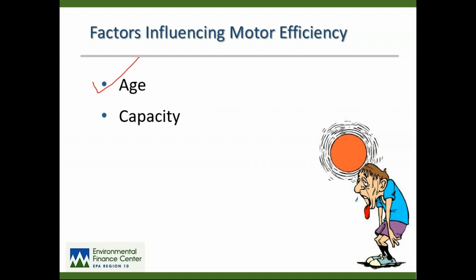The first one is age. We just talked about that. Generally, the older the motor is, the less efficient it is. The second is the capacity of the motor. If you have a 5 horsepower motor, it's very typical you might have 75 or 80% nameplate efficiency that the manufacturer gave you. If you buy a 1,000 horsepower motor, typically you're going to see 93, 94, maybe 95.5%, especially if you buy what's called a NEMA premium efficiency motor. I'll talk about that in a few minutes.